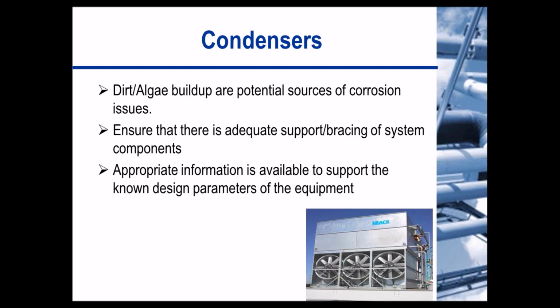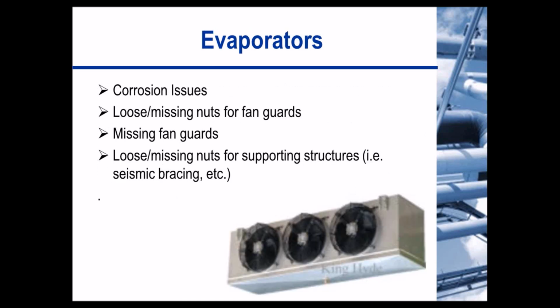So when we consider condensers, we see that dirt and algae buildup are potential sources of corrosion issues. Here we want to ensure that there's adequate support and bracing of the system components, and also that appropriate information is available to support the design parameters of the equipment. For evaporators, the typical issues, like the other components, were corrosion issues. Also, loose or missing nuts for fan guards, missing fan guards, or loose or missing nuts for supporting structures.